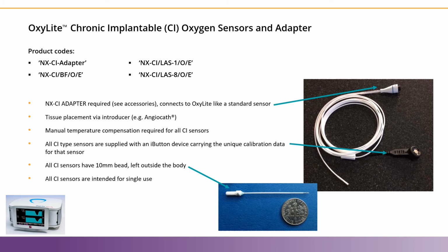This information is usually stored in the connector of the standard probes, but since these CI sensors don't connect directly to the OxyLite, the calibration info for each sensor can be quickly loaded onto the system with the simple click of a button. All CI sensors have a 1 centimeter long white bead that must remain on the outside of the body, and all of them require manual temperature compensation. These sensors are intended for single use.